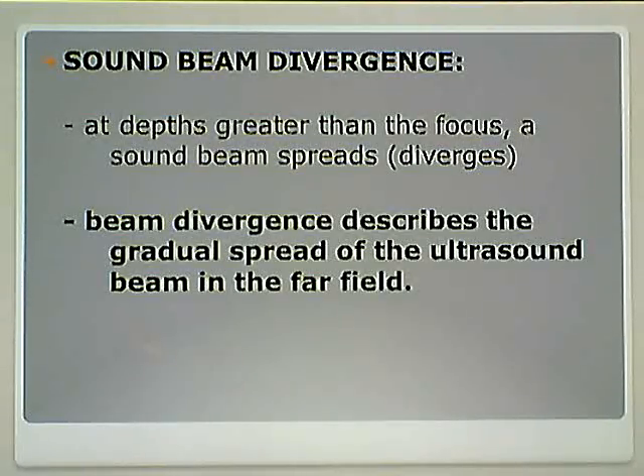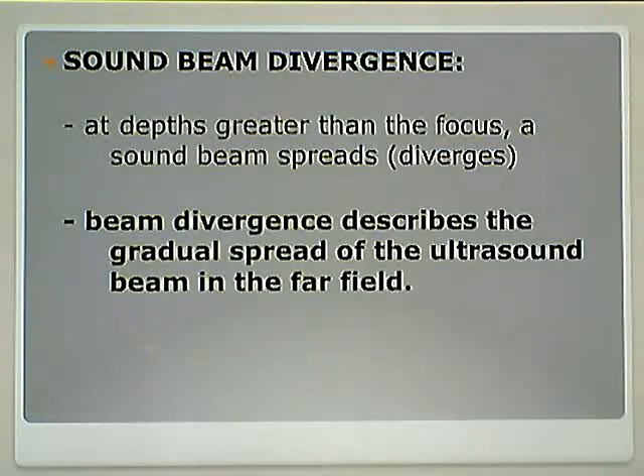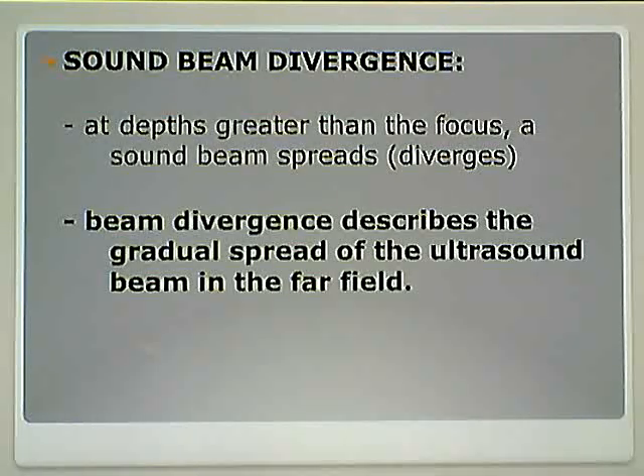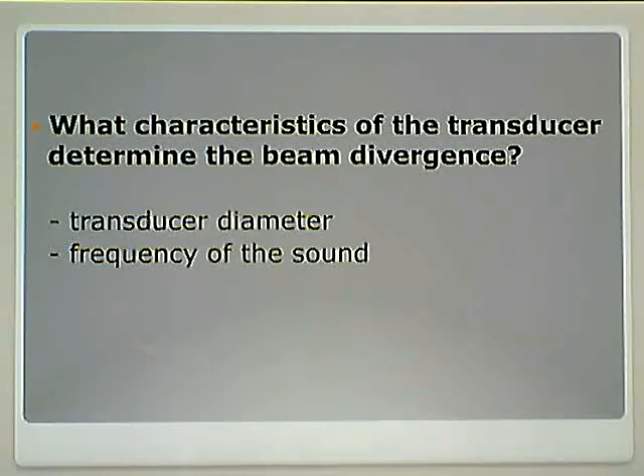Sound beam divergence. At depths greater than the focus, a sound beam spreads or diverges — the focus is the narrowest point, so beyond it the beam has to start diverging or expanding. Beam divergence describes the gradual spread of the ultrasound beam in the far field. What characteristics of the transducer determine beam divergence? Again, transducer diameter and frequency of the sound.